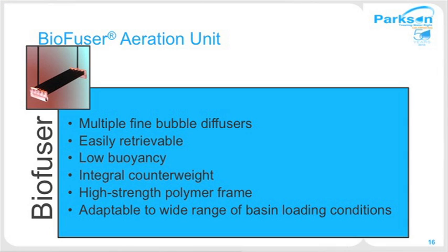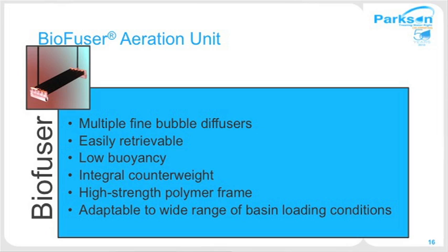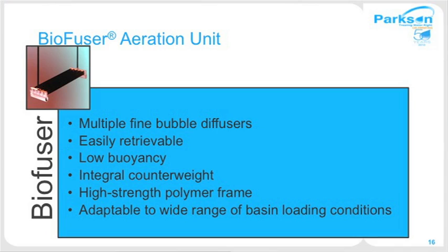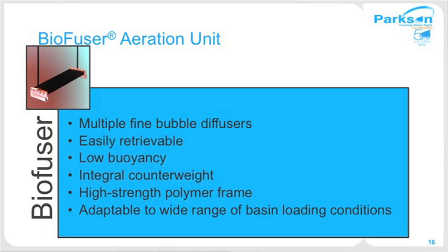Here's a closer picture of the biofusers — the heart of the BioLac system. Biofusers contain multiple tubes, up to five aeration tubes per biofuser unit, balanced with two downcomers from the side for consistent oxygen transfer efficiency throughout the tubes. They're very easily retrievable because they're not mounted on the bottom. For maintenance, an operator on a boat can retrieve the diffuser to the surface — there's never a need to drain the basin. Sometimes integral weights are added to keep the biofuser at the bottom. The design allows easy future expandability by adding up to five diffuser aeration tubes.